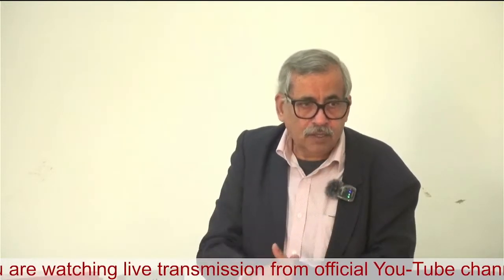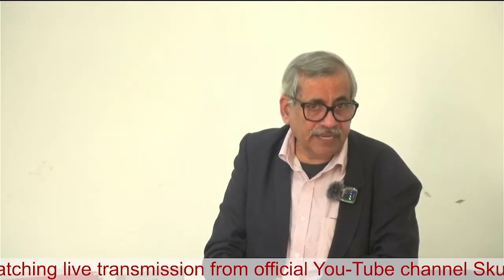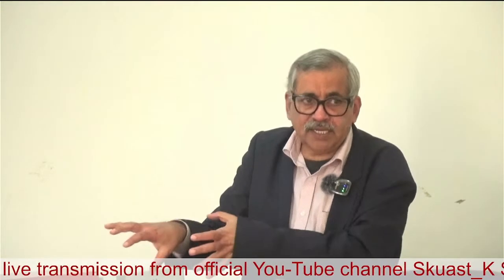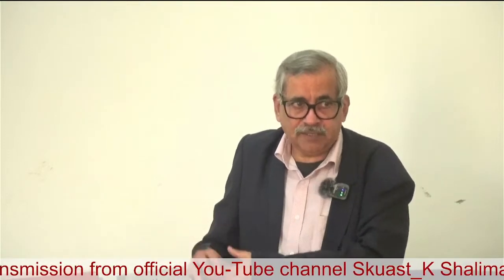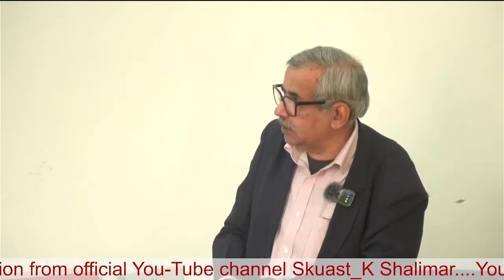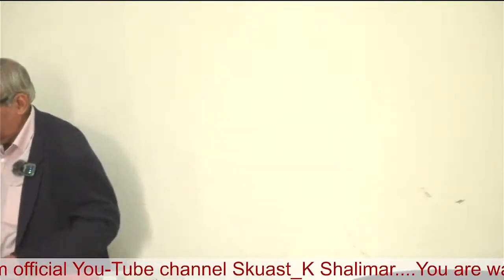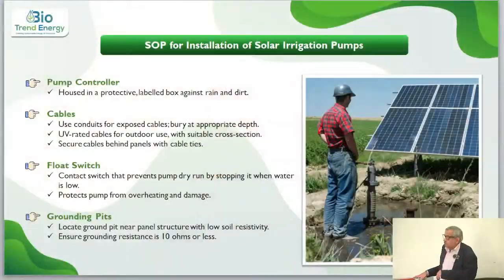So tomorrow, if some pump has to be maintained or some service is required, you can dismantle it through this union. Proper insulation of all electrical connections is critically important during the installation of solar pumps. And the pump controller, very importantly, is housed in a protective, labeled box against rain and dirt, because this is the electronics part. Water and moisture will affect its operation, and it has to be kept clean from the dust perspective.